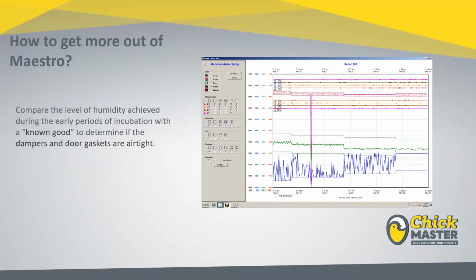Another thing that can cause inconsistency in machines is not having good closed sealed dampers, or not having dampers that function completely controlling the volume of air going through the machine. And we'll monitor or look for issues with that based on looking at the humidity level. So in this case, we see that we have a fairly normal humidity curve where it's following the set point and the damper is controlling this. But if I have a machine that is having an issue, I may see that here I was probably leaking a little bit of air through the machine, not allowing the humidity to get anywhere close to the set point. And this is at a time period where you have a relatively low damper opening.